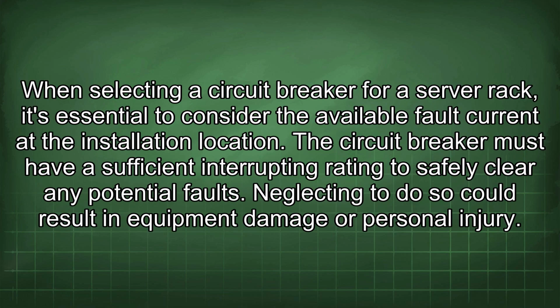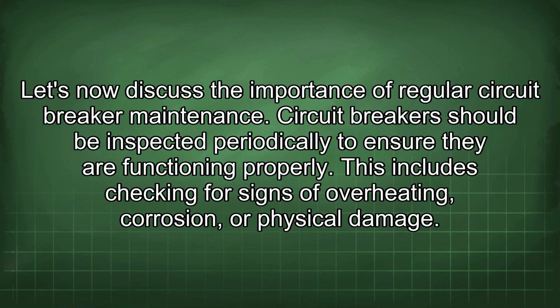When selecting a circuit breaker for a server rack, it's essential to consider the available fault current at the installation location. The circuit breaker must have a sufficient interrupting rating to safely clear any potential faults. Neglecting to do so could result in equipment damage or personal injury. Let's now discuss the importance of regular circuit breaker maintenance.